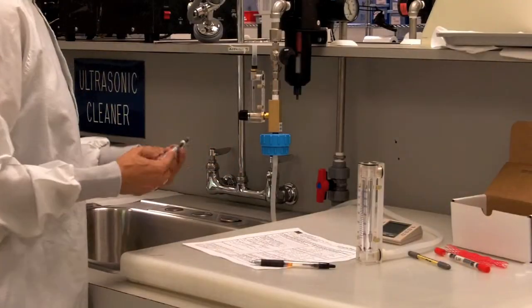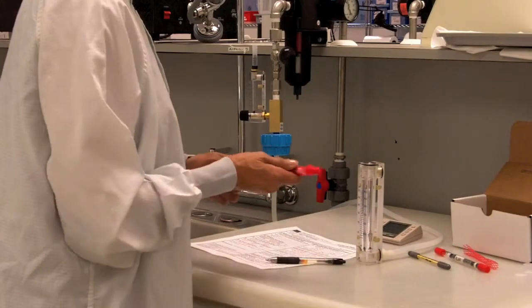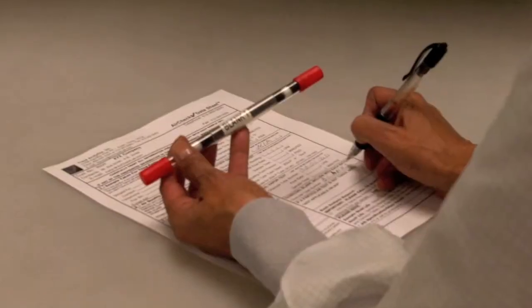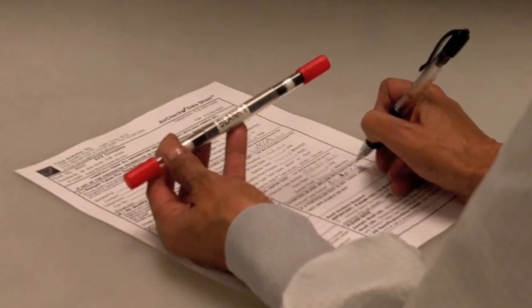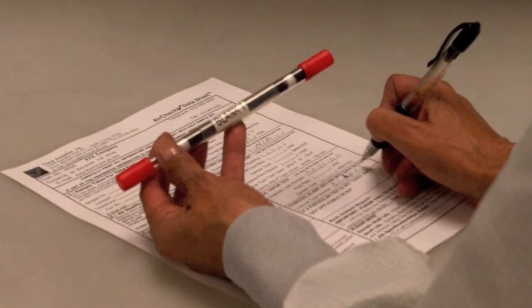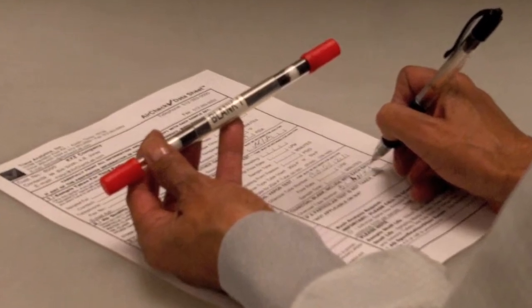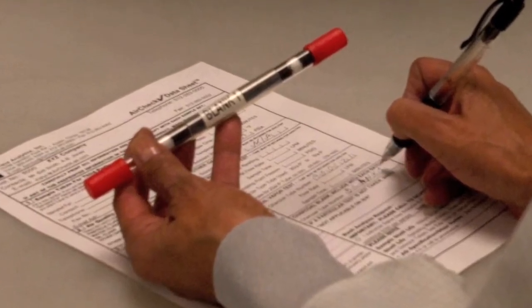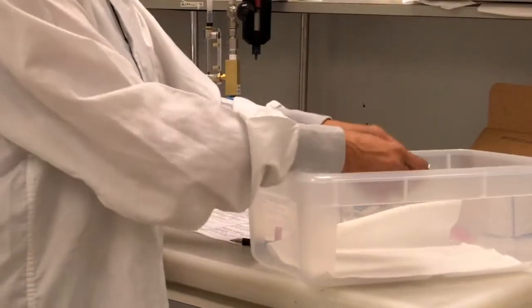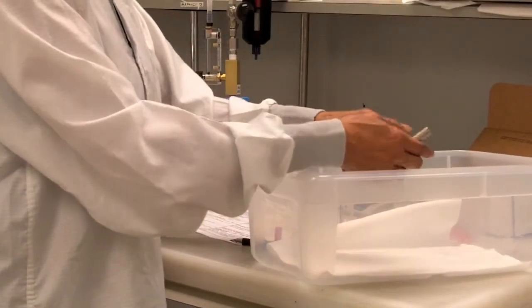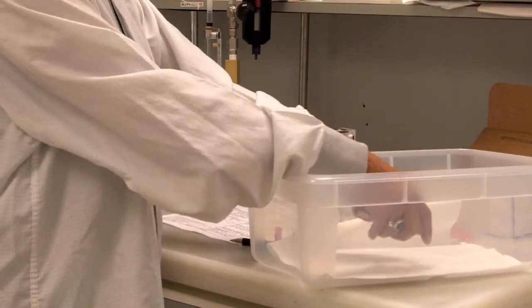At the end of the sampling time, remove the tube, cap both ends of the oil vapor tube, apply the netting, and place the tube in the pre-addressed return mailer. Record the flow rate and sampling time on the datasheet. Only one blank needs to be submitted per batch of samples taken on any given day. Simply break both tips off an oil vapor tube marked blank, cap both ends, note on the datasheet, and place in the return mailer.